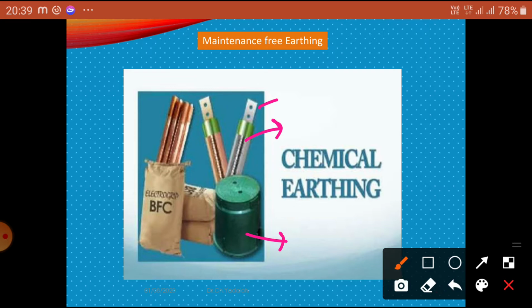Chemical rod earthing uses a bentonite-based or graphite-based compound along with the earthing electrode, a pipe or rod, that helps improve the soil condition and reduce soil resistivity. The prime contents include bentonite, graphite or aluminum, silicates and metal powders. These maintain moisture in that area.